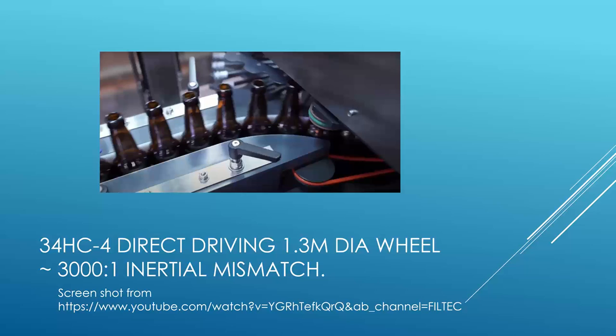Here's an example of a direct drive. This is a bottling machine, and this is about a 3,000 to 1 inertial mismatch. It's about 1.3 meters, and what they're doing is slowing the bottles down so they can take a picture of the inside of each of them and make sure everything's clean, there are no chips, for recycling bottles. It's direct drive straight off the shelf. There's no gearhead on this. So this is an example of what you can do. A lot of them take the encoder readings directly off of our motor to time all their cameras, saving multiple components. And these have been very, very solid.